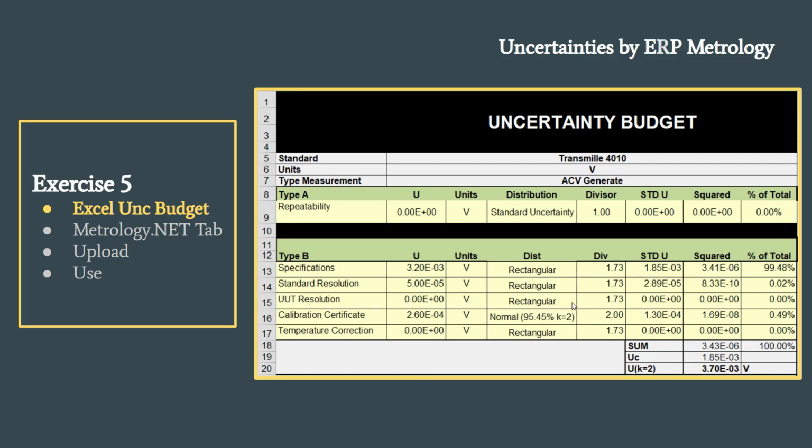The goal here is that it allows you to calculate measurement uncertainties however you want to, and you're able to override the measurement uncertainties produced by CalLab Solutions with your own uncertainties as you're doing the calibration. This is the main part of the sheet, and I'll bring a sheet up as an example once I go through all of these pieces.